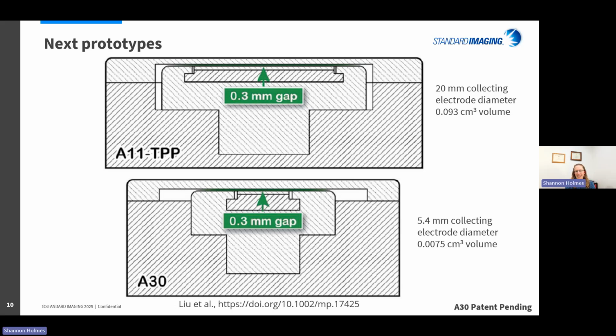If we can calibrate it in cobalt and calibrate it in the ultra high dose per pulse radiation, then that's a great validation of that ability to span the gap as well. So I look forward to those protocols, but I know that they don't exist yet.